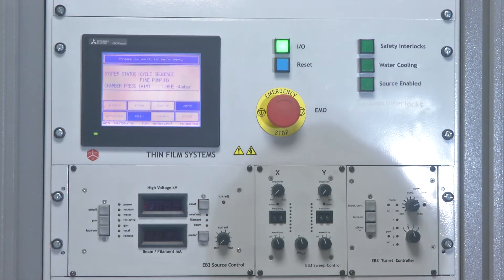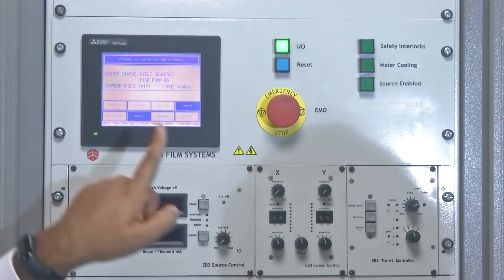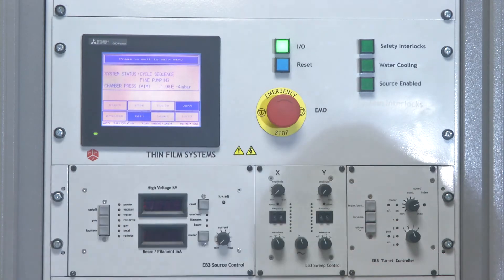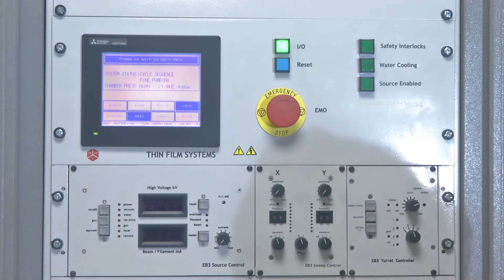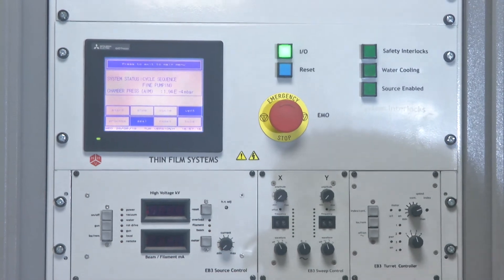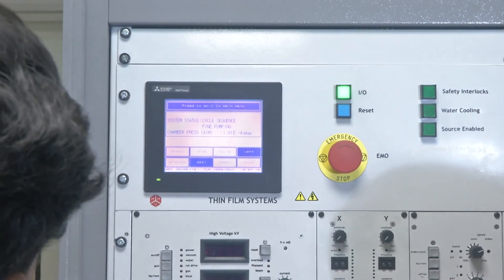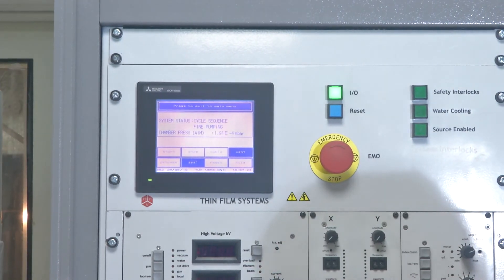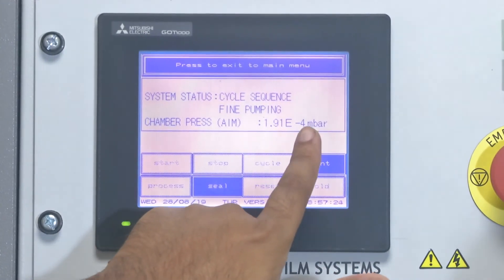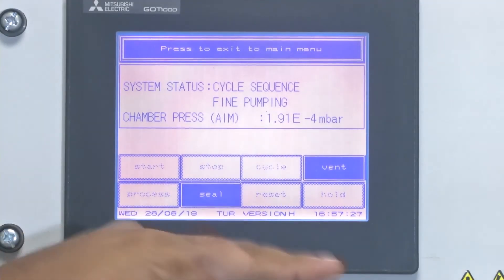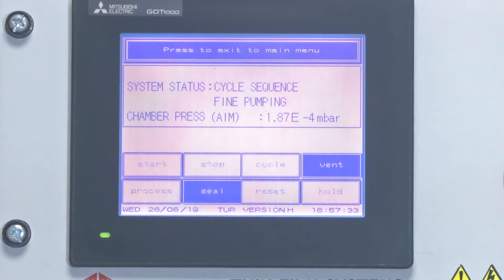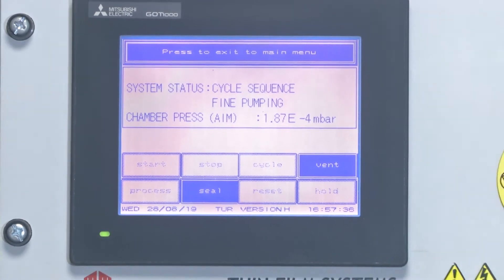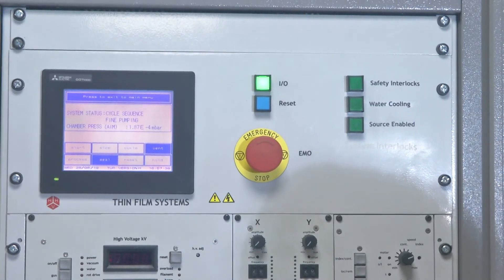The vacuum and water flow switches must all be satisfied — all must be in normally-closed condition. The chamber vacuum currently reads 1.91 times 10 to the minus 4 millibar. It needs to reach 10 to the minus 5 millibar for the turbo pump and for the process to start. At that point all those indicators will turn on, and we have to wait. As we create higher vacuum, it becomes progressively more difficult.